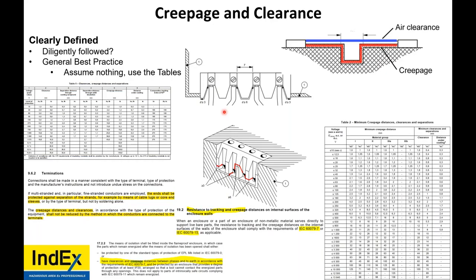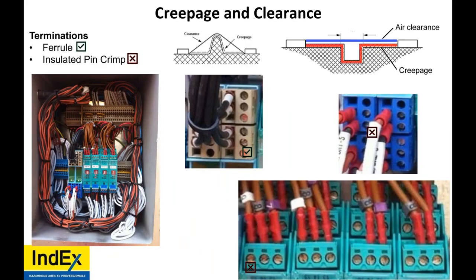Diligently followed? No, because who gets this table in the field? No one. But if we're looking at EXEB for a group 2 for 1,000 volts, we're looking at 25 millimeters of minimum creepage distance, and clearance, we're looking at a minimum 14 millimeters. That's a big space. Now, sometimes people remember a 6 millimeter rule. 6 millimeter only applies at 250 volts, and that's 6.3 for creepage. Once you get up to 400 volt, you're at 10 millimeters. So trying to remember these tables is not practicable. So, creepage and clearance distances.